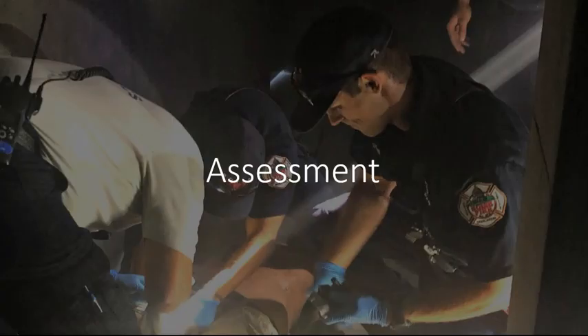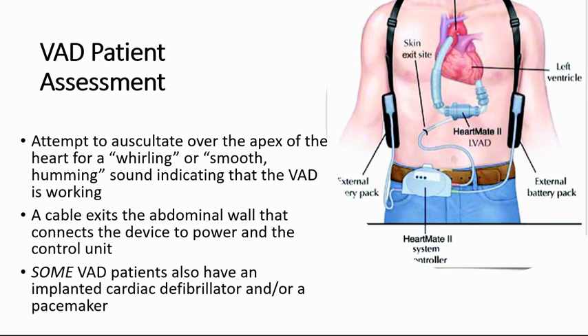Let's talk about assessment. When you're assessing the LVAD patient, the very first thing you should do, like a pulse check, is take out your antiquated stethoscope and listen over the chest at the point of maximal impulse or close to that. So basically fourth intercostal space, maybe a little bit lower, mid-clavicular line. And you should easily hear a whirling sound or a humming sound. You may even be able to feel it.